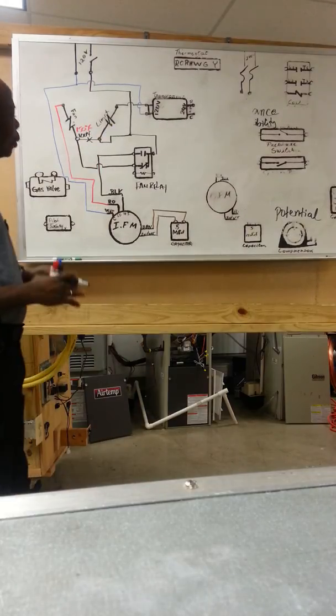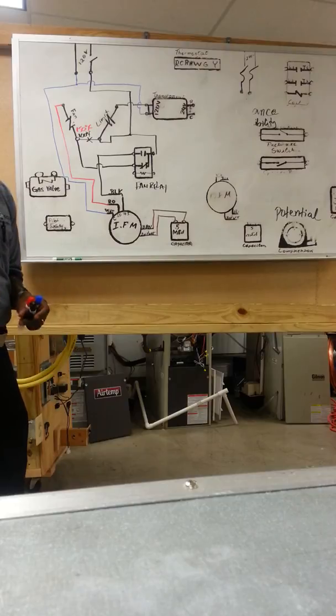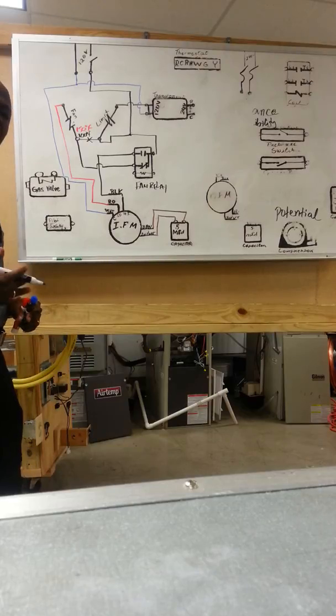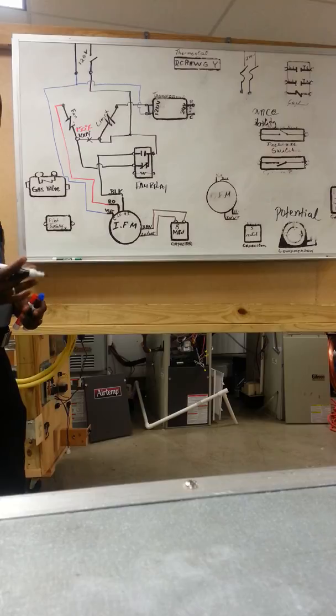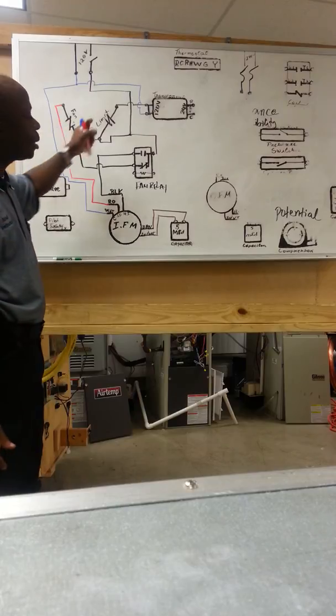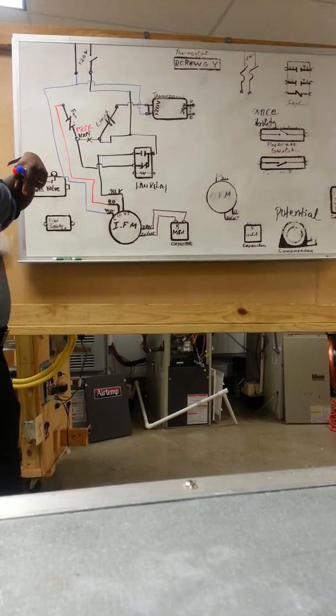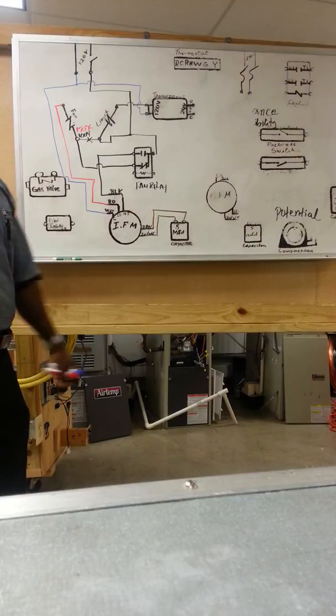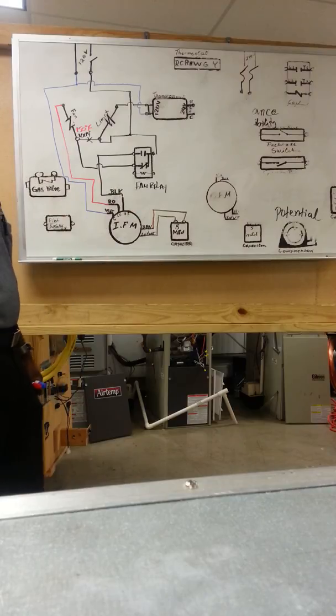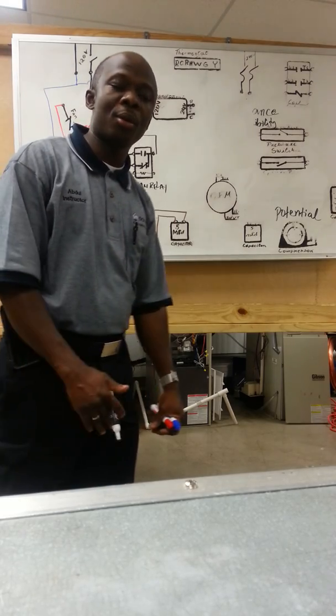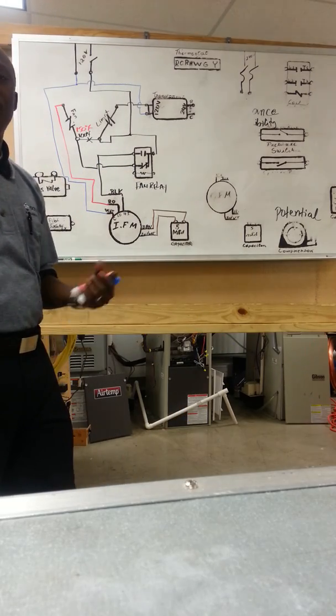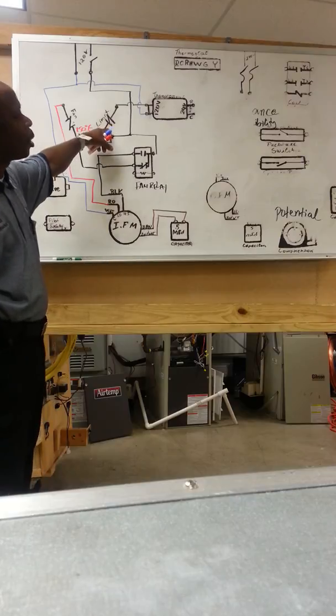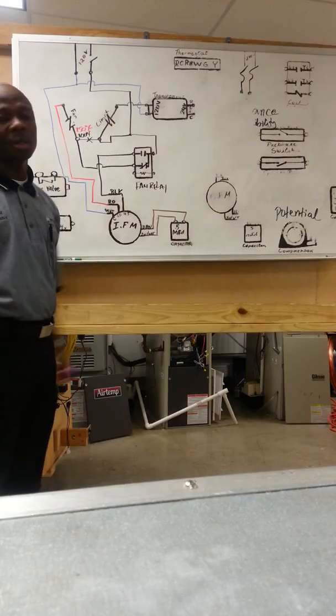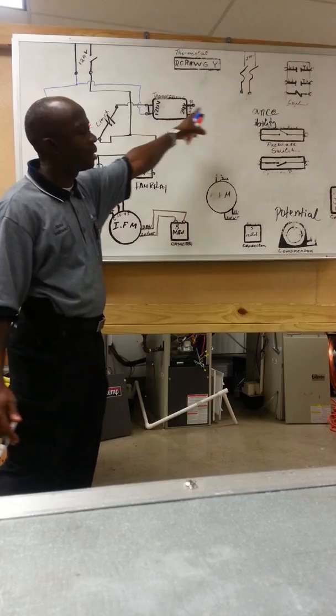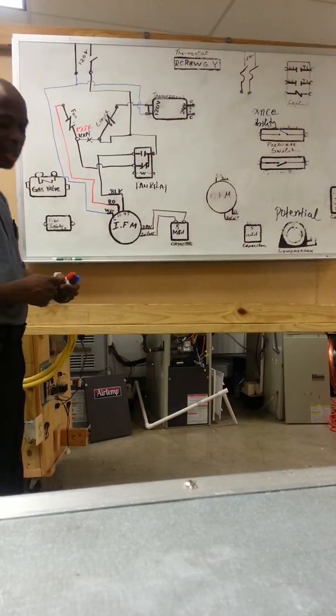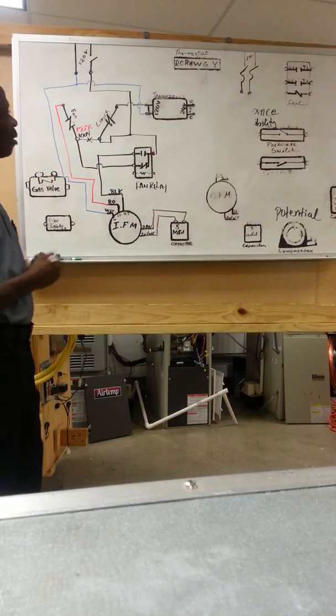The limit side is going to stay closed, hopefully if everything is good. If that limit side breaks in a closed position, what happens? It will not turn the unit off. The burner will keep burning. Thermostat temperature, you may have set it to 77 degrees, and you come into the apartment or house, the temperature is 105 degrees because the limit is broken in a closed position. It's not cutting the gas off because the transformer is still sending 24 volts to the gas valve. Let's see how this 24 volts goes to the gas valve.